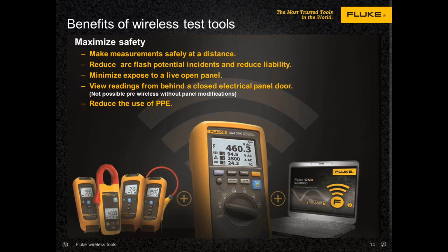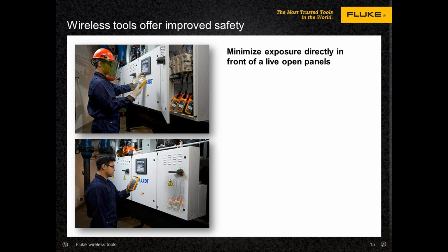The slide earlier that we showed you with the technician with an arc flash hood on, it's very hard to see the meter readings through that tinted shield. Once you get this stuff installed, you can take your hood off and see everything just fine. Previously, it's not been possible to view live readings inside a panel with the doors closed.